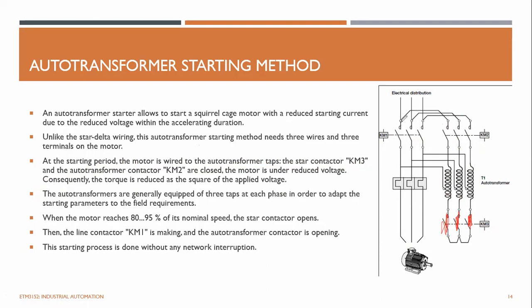So the current goes through this transformer, and whatever the voltage applies to the motor, and then the contactor KM2 is closed. So this one is closed. Now you can see the 3-phase wire comes here and makes a transformer connection like a voltage divider. There's a voltage drop here and a voltage drop here. And this voltage from here to here will be applied to the motor, right? And the rest of the voltage is dropped across the transformer coil on this side. But by changing the tapping, you can change this desired voltage.